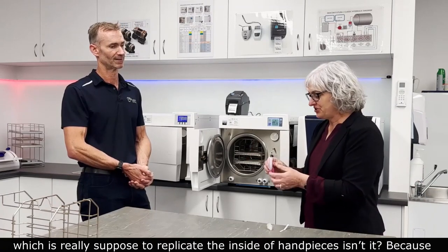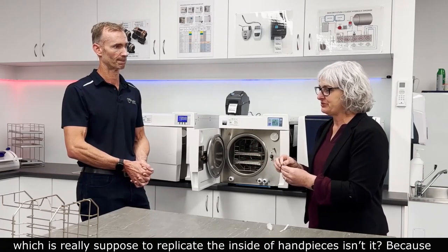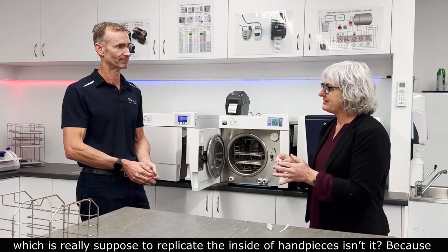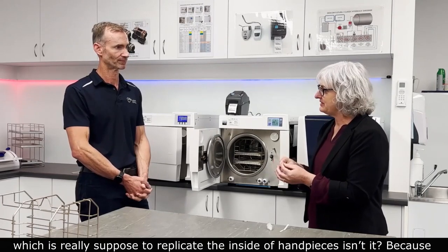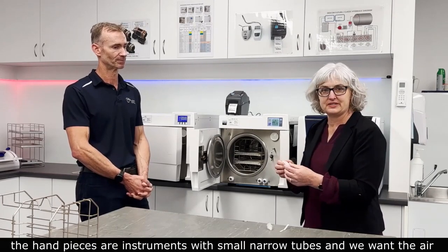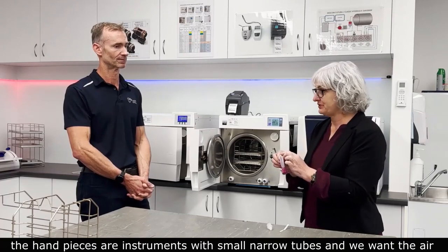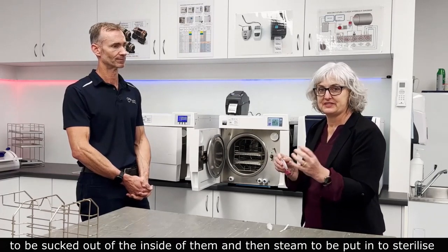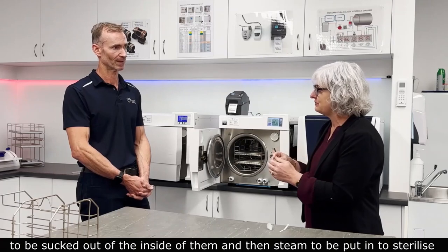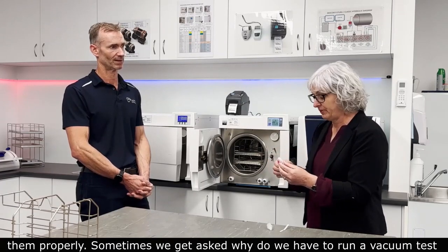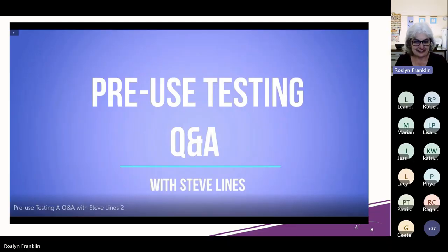Tiny tubing, which is really supposed to replicate the inside of handpieces, isn't it? Yeah, because handpieces are instruments with small narrow tubes, and we want the air to be sucked out of the inside of them and then steam put in to sterilize them properly. Yeah, so that little snippet.